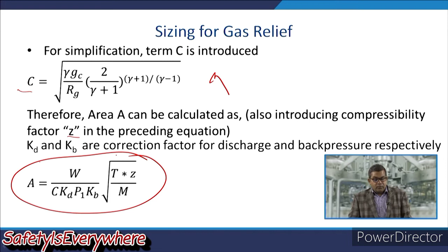Conventionally, we can calculate C by this particular equation by substituting the various values in the previous equation. Now, C is equal to 519.6 into square root of gamma into 2 upon gamma plus 1 to the power gamma plus 1 upon gamma minus 1. We have to note that for using this formula, the unit of W is pounds per hour, P is in PSIA, T is in Rankine, and M is in pounds per pound mole. They must be put correctly, and while doing such calculations the consistency of units must be remembered.